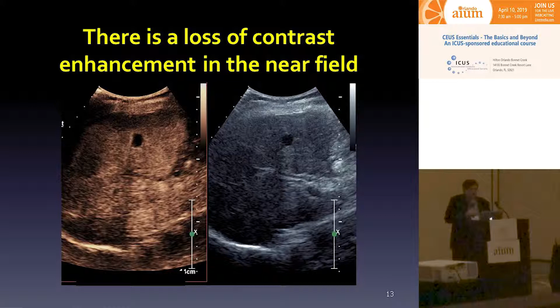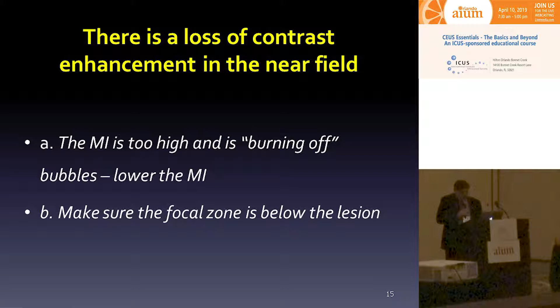So again, the MI is too high and you're burning off bubbles. You need to lower the MI. I think this was more of an issue in older equipment. As we've come to newer equipment where the MIs are standardly lower, we're not seeing this effect too much. And again, as Andre showed you, the focal zone can make a huge change. You should always have the focus zone in the far field, either below the image or at the bottom of the image, because that can also cause this effect.